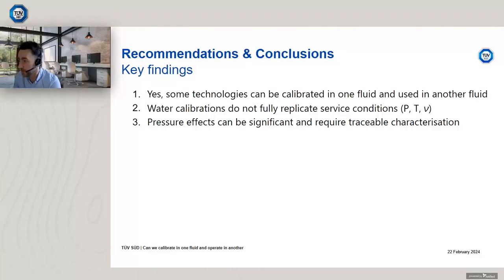Pressure effects can be significant and require a traceable characterization. So Coriolis meters do have a pressure effect. It's known. Various manufacturers now publish their pressure effect. However, in a lot of cases, you still want to then derive your own traceable characterization for that individual device.